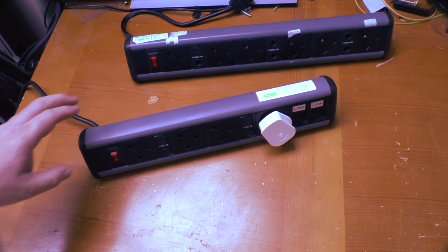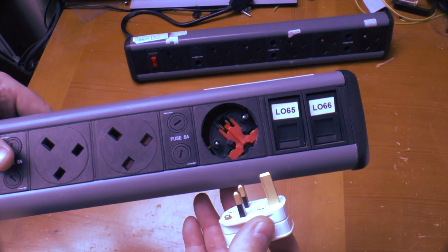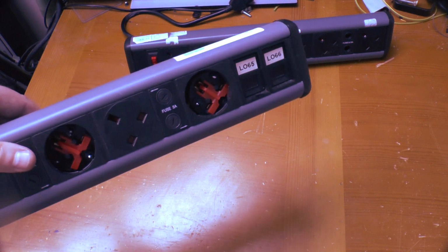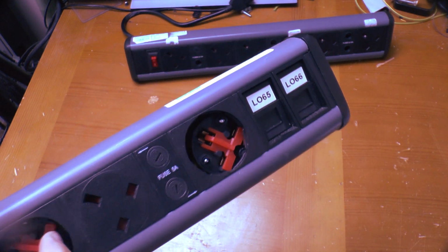This one though, this one's a cracker, literally. Following the lockdown last year, some staff came into the office to collect their computers and other equipment to work from home. When the members of staff unplugged from this one, the faceplate pulled clean out of the socket. Twice. And one of my colleagues has seen these as well. So this isn't the only one we've got in service. He's seen others fail in the same way. And those are bare contacts in there.